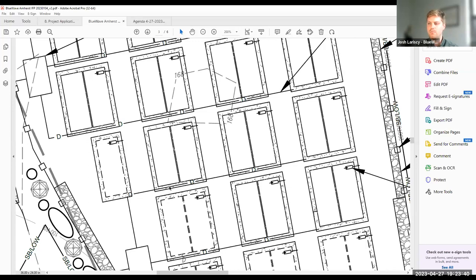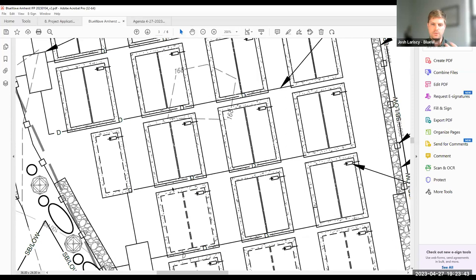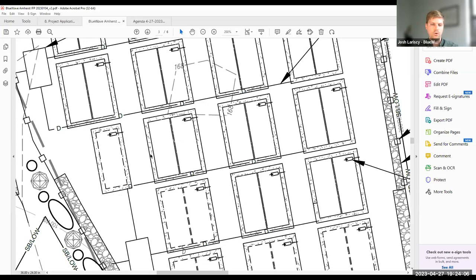Speaking with the Conservation Commission, the concern was containment over potential electrolyte leaks from the battery cells. In normal operation, we don't expect any electrolyte to leak in material amounts from the cells or the enclosures, so it's basically just water falling on the edges of the pads or the container rooftops that sheets off onto the lip of the pad.